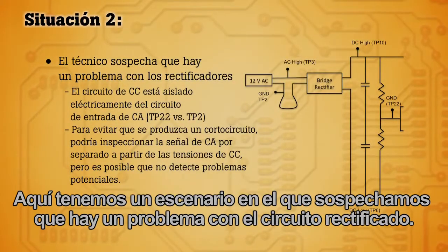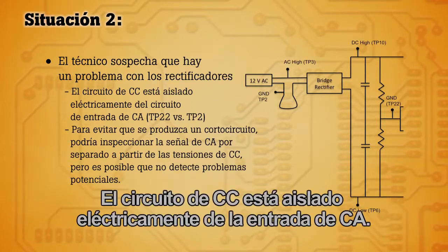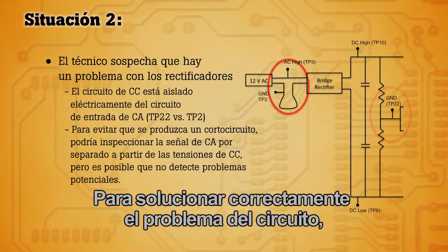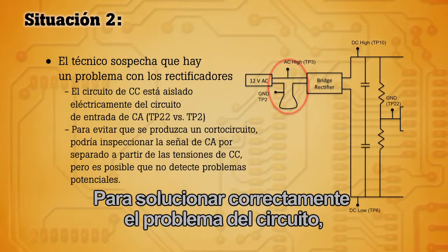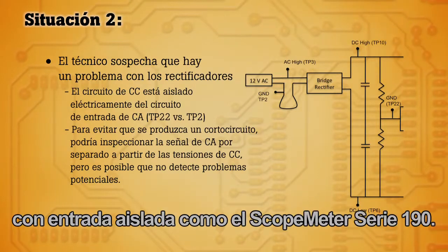Here we have a scenario where we suspect that there is a problem with the rectified circuit. The DC circuit is electrically isolated from the AC input. In order to troubleshoot that circuit correctly, it's best to use an isolated input oscilloscope like the ScopeMeter 190 series.